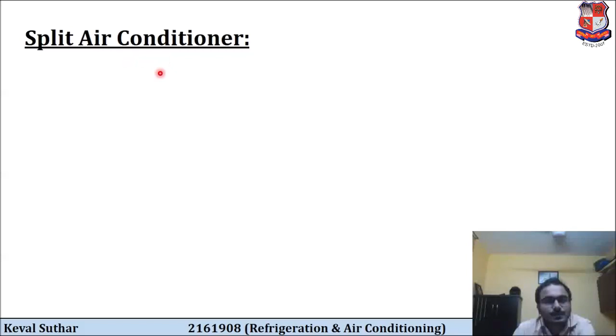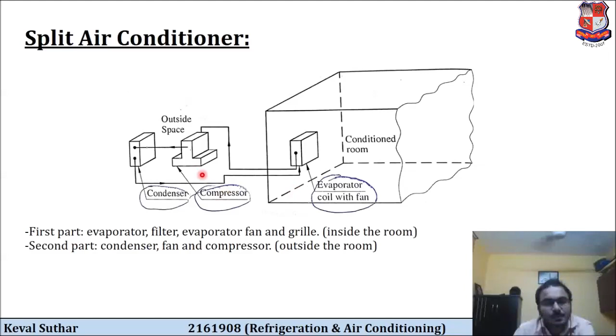Here, as you can see, this is conditioned room or space, and here we are having only evaporator coil with the fan, and the remaining parts are in the outside space where we are having condenser and compressor as shown in this figure. So only the part which is doing conditioning is kept here, and the remaining parts are kept outside. So the first part is this, that is inside this conditioned room. It contains evaporator, filter, evaporator fan and grill, and these are inside the room. The second part is this, which contains condenser, fan and compressor, which is outside the room. So this is the split air conditioner basic air conditioning system.